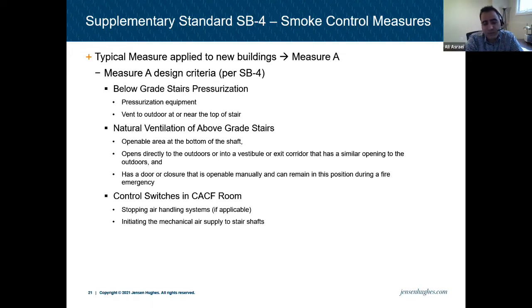And on a lot of occasions you see automatic door openers that open at the bottom of the stair, and no fan is in it necessarily. It's just natural ventilation, which is acceptable since the building is sprinklered. I don't know how practical it is, but it is the building code. Because sometimes in the winter, if you do the test, there's a lot of pushback of the air going into the stair instead of the air going out. But it is permitted in the code based on measure A.